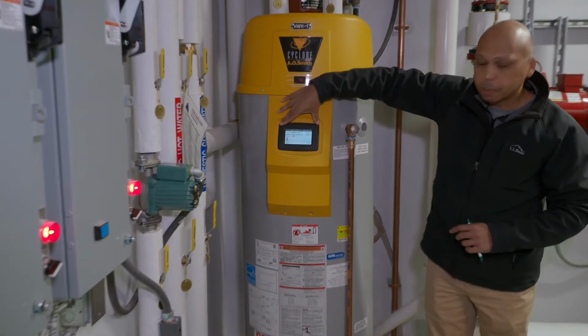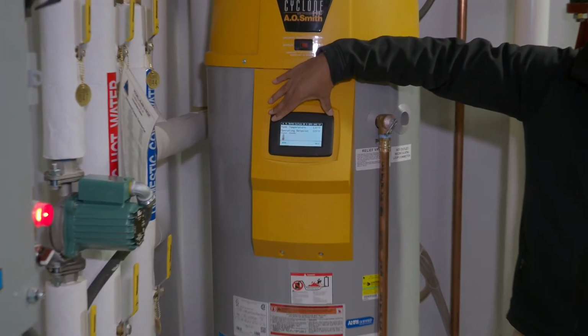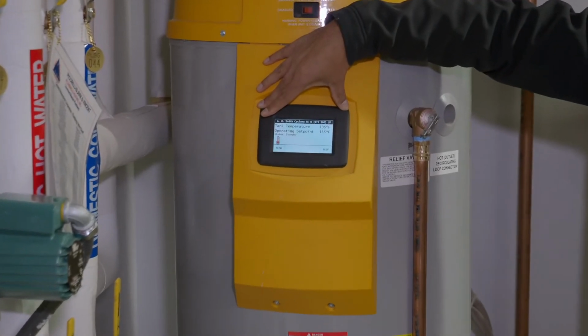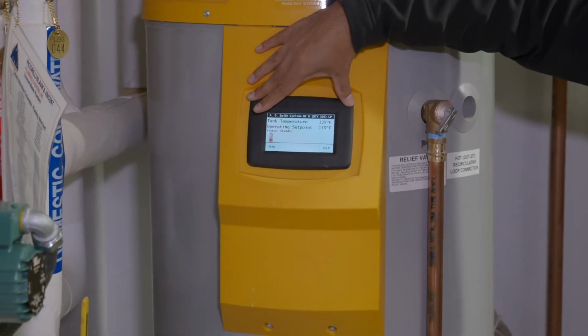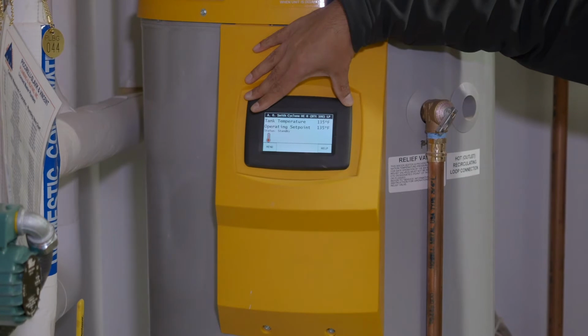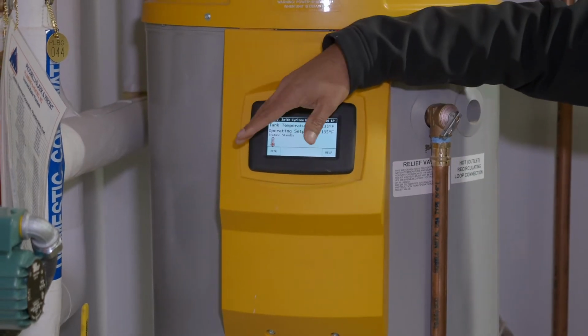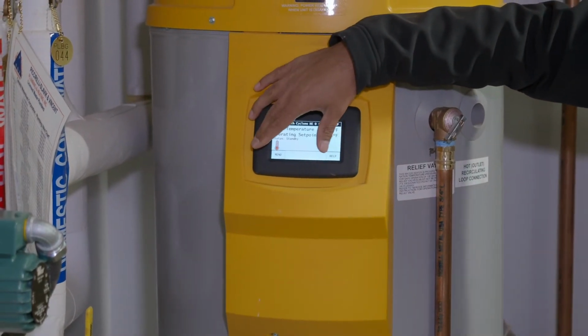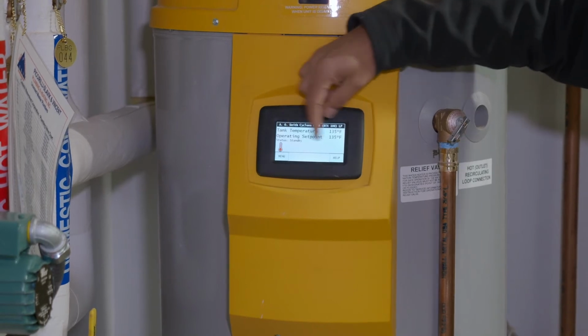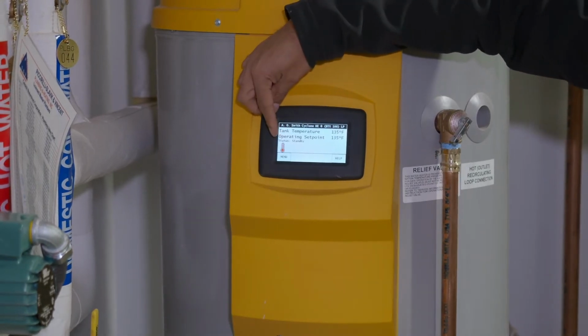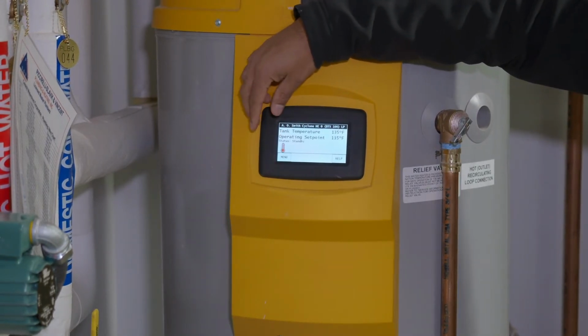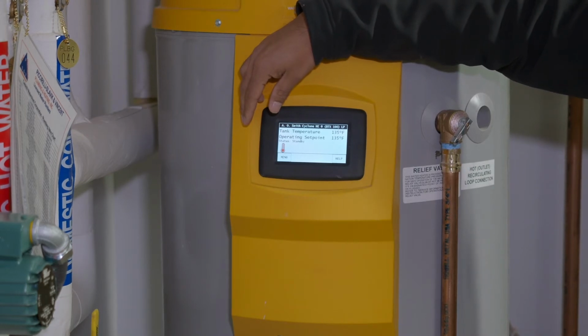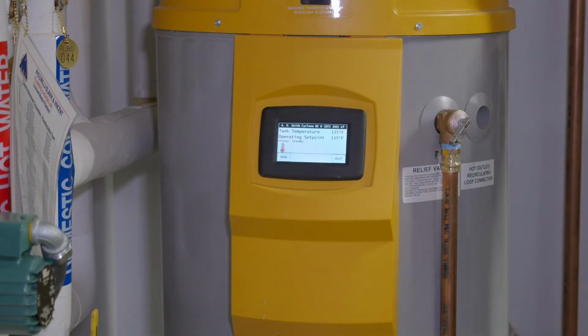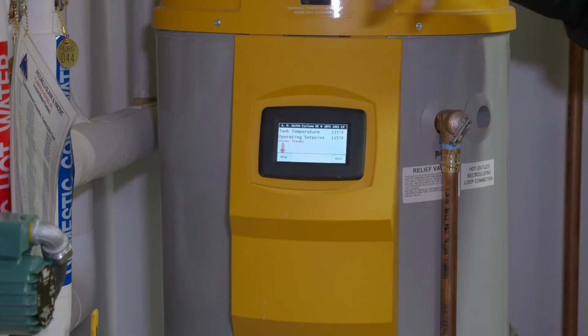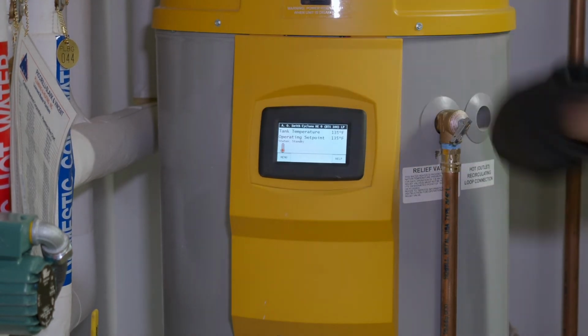Also here you have your touch display. On this touch display, it's going to show you a couple of things. It's in normal operating mode, standby mode when it's just sitting there waiting for a call for hot water, and any error codes are going to pop up through here. You'll see a couple of icons. You'll see one icon right now is a temperature symbol. You'll also see a fan when the blower kicks on to make sure the flue pipe is free and clear. And you'll see a flame signal.